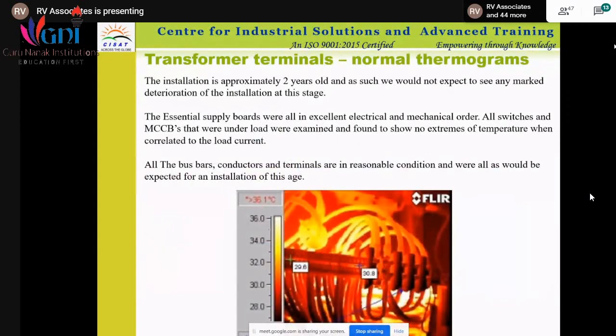This is a picture. I hope it is clear to all of you that all these pictures are practical case studies. This is the picture of transformer terminals, where one of the terminals is getting heated. Why is it getting heated? It may be because of a loose connection. It can be because of imbalance of the current, the symmetrical load and unsymmetrical load concept comes here. Because one phase is overloaded, it will get heated. Or the brazing, meaning the connection of the terminal, is loose, it will give you continuous arcing. That arcing may lead to a fault, or it can cause a rise in temperature. So that is to be identified or analyzed by yourself.